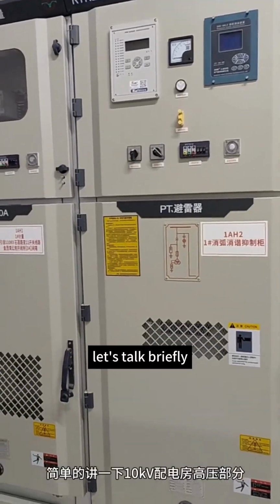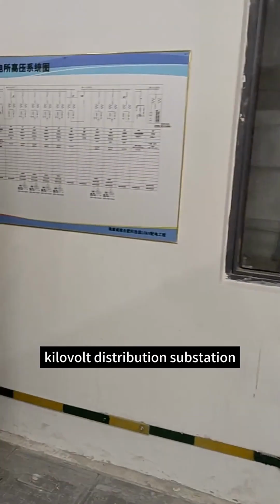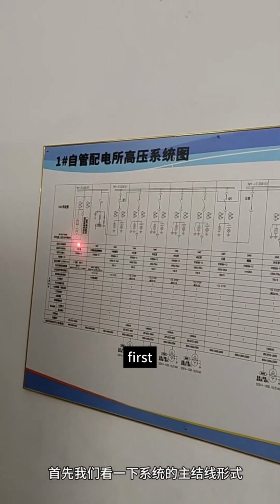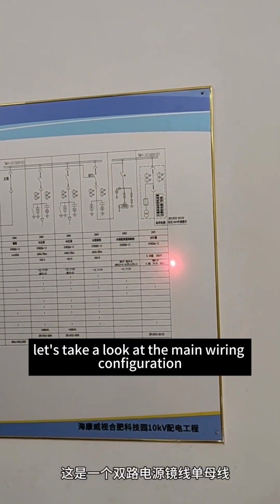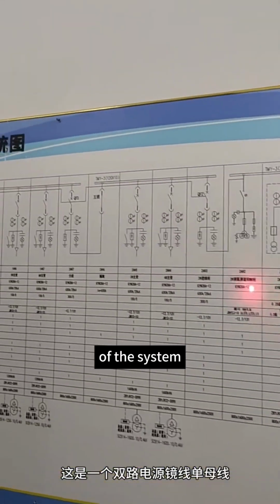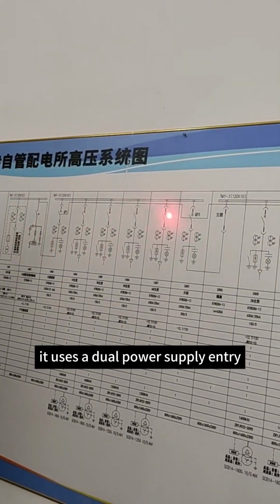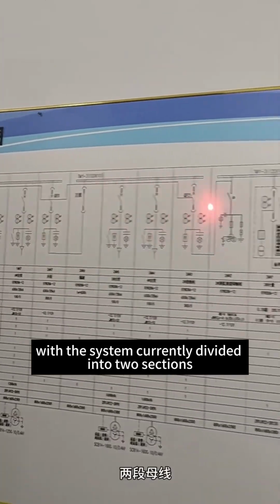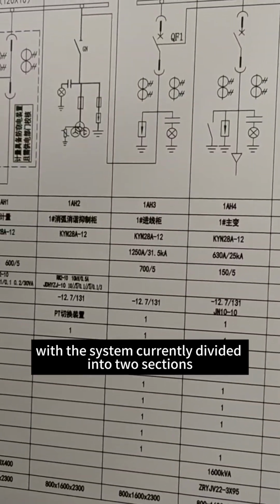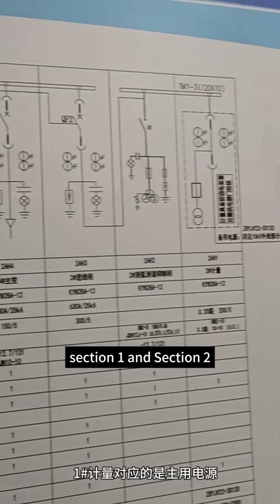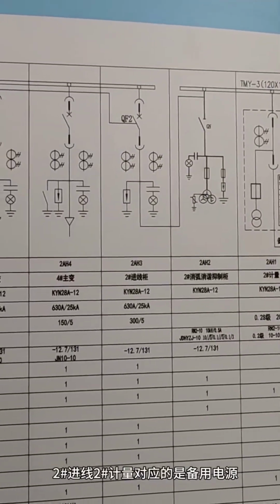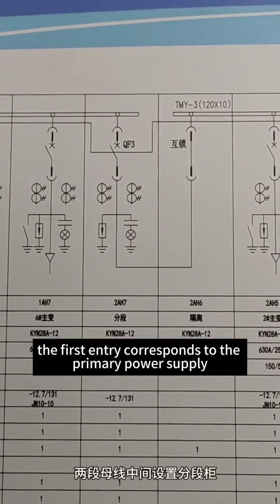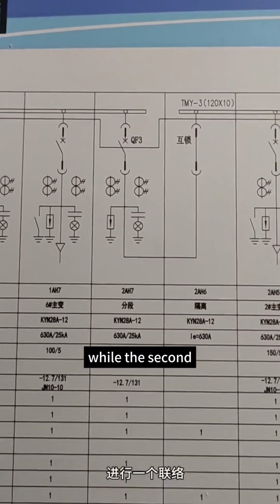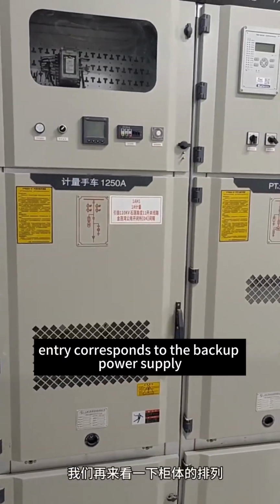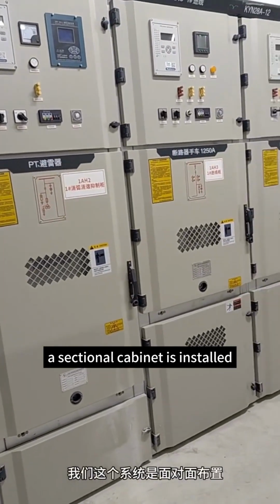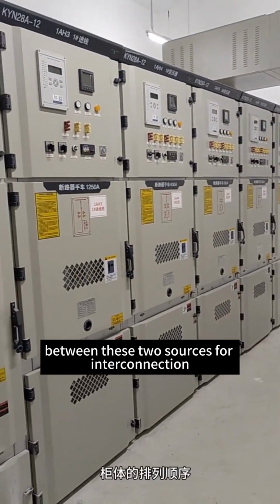Let's talk briefly about the high voltage part of a 10 kilovolt distribution substation. First, let's take a look at the main wiring configuration of the system. It uses a dual power supply entry, with the system currently divided into two sections, Section 1 and Section 2. The first entry corresponds to the primary power supply, while the second entry corresponds to the backup power supply. A sectional cabinet is installed between these two sources for interconnection.